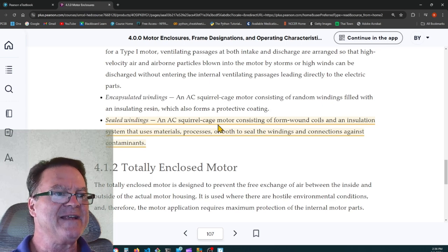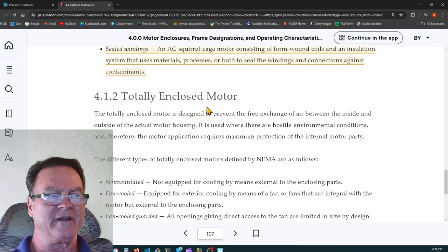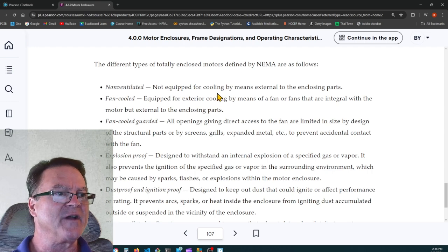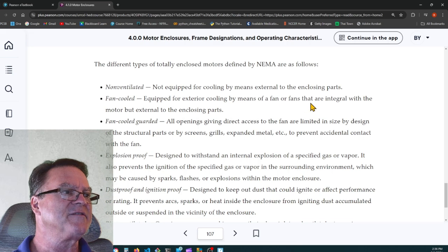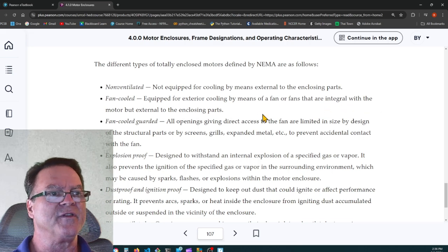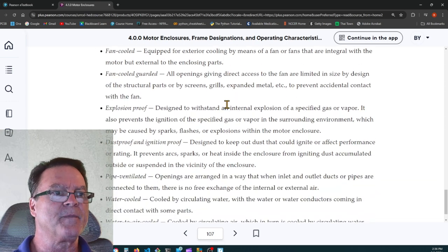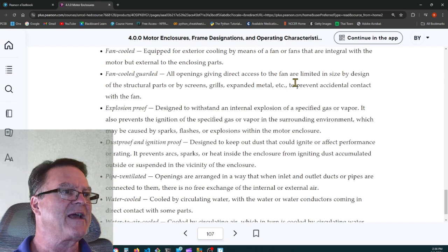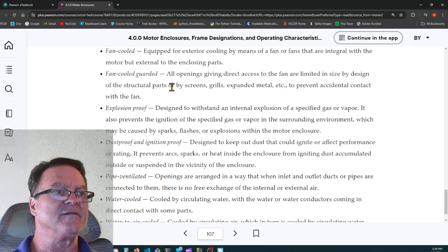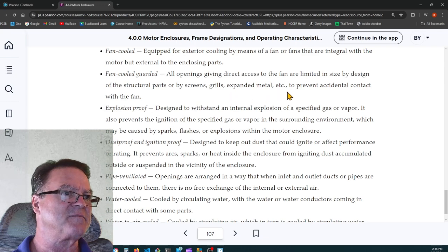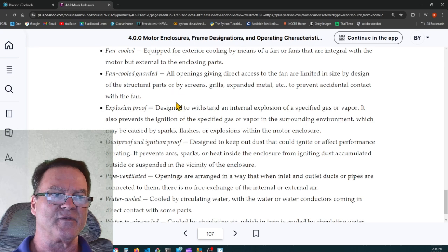Sealed windings. Here's a highlight. It says an AC squirrel cage motor consisting of form-wound coils and insulation systems that uses materials, processes, or both to seal the windings and connections against contaminants. Then we have totally enclosed motors. Non-ventilated: these are not equipped for cooling by means of external air to the enclosed parts. Fan cooled: they're equipped for exterior cooling by means of a fan or fans that are integral with the motor but external to the enclosed parts. Fan cooled guarded: all openings giving direct access to the fan are limited in size by design of the structural parts or by screens, grills, expanded metal to prevent accidental contact with the fan.